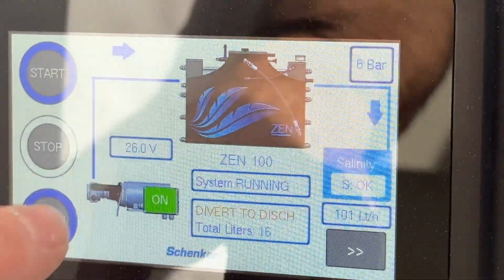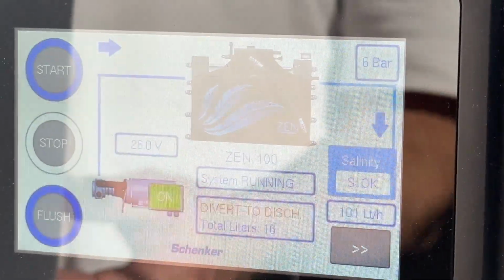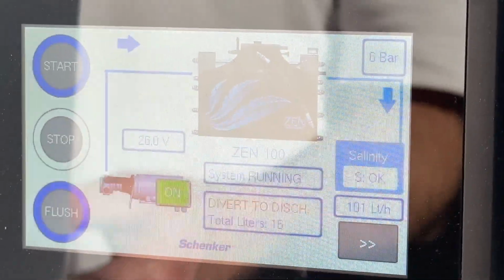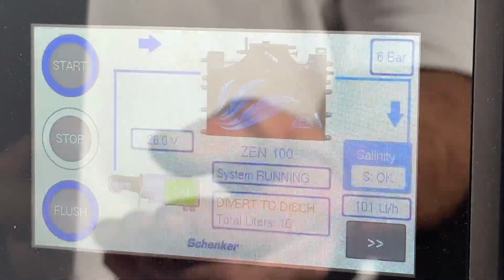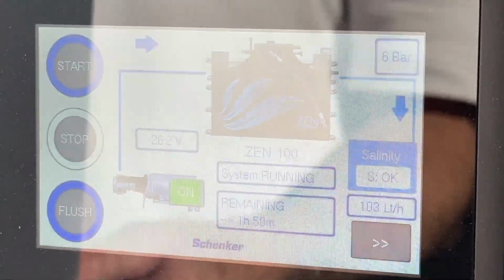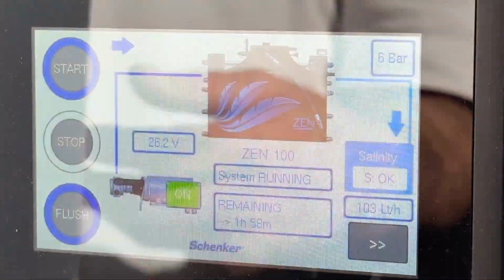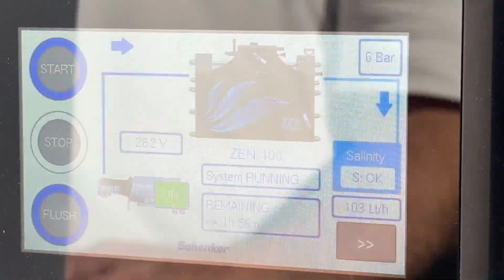Things that will affect the pressure would be battery voltage, temperature of the seawater, and salinity of the seawater. The colder the seawater, the higher the pressure with a slightly lower output, because cold water is more dense, so it requires more pressure to push it through the membrane.